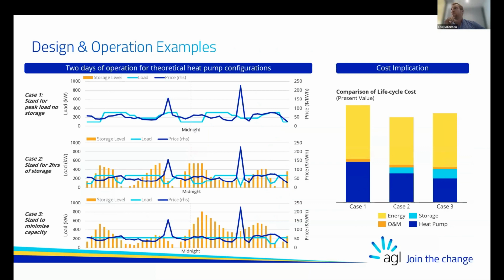In case one, the system's been sized for capacity, and this is something Jared will tell you straight away not to do. You can get away with it, but you can do better. In that instance, you've got no storage, so you've got to follow your heat load consistently. There's some wiggle room, but not much flexibility. You can't move your heat load around, and you're also sizing the system, the most expensive capex component, as large as you need. So this is sort of the worst case scenario.